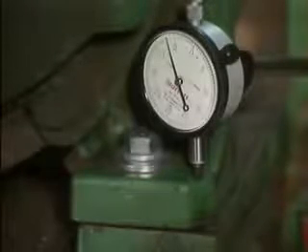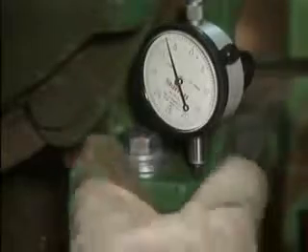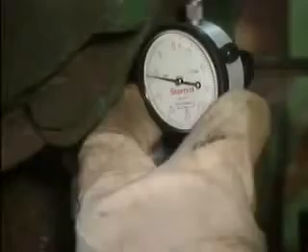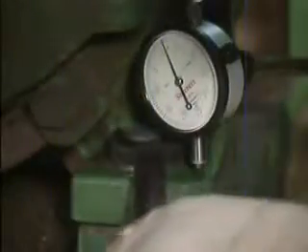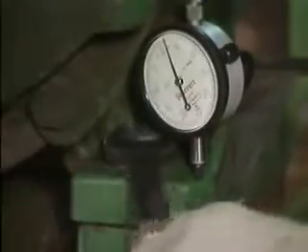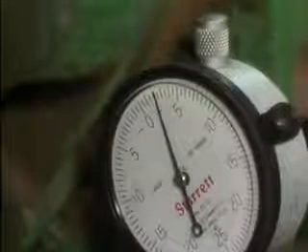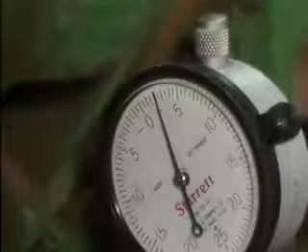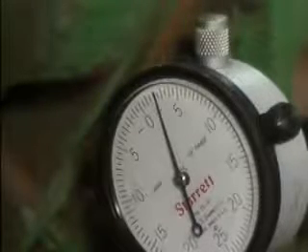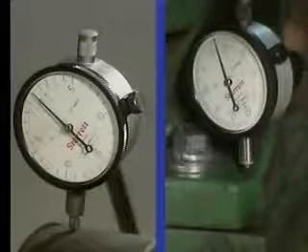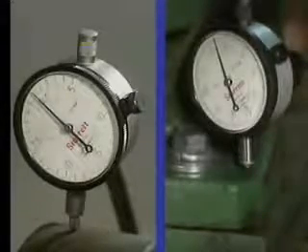Each dial indicator is mounted so that its stem is partially compressed before the indicator is zeroed. Doing this ensures that each dial indicator will be able to detect movement during the procedure. Next, the hold-down bolt on the first foot is loosened, and the dial indicators are checked. If either dial indicator detects more than the allowable limit of movement, which at many plants is 2 mils, then the foot is soft. To understand why two dial indicators are preferable, we need to look at some illustrations.